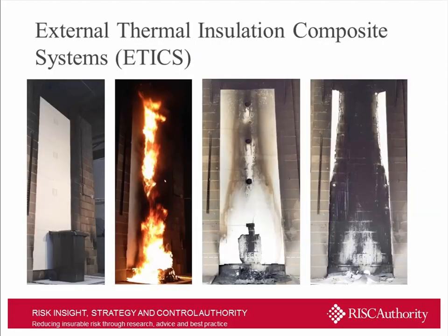As you may be aware, RISCAuthority has been running some tests on these external thermal insulation composite systems, and there are reports available, I understand, that describe the tests. There are just a few images on the screen there that show that in the event that you do have a fire, we were using a source that's a wheelie bin full of rubbish. But in the event that there is a fire, depending on the circumstances and depending on the standard of installation and the number of penetrations through the render covering, the fire will behave very, very differently.